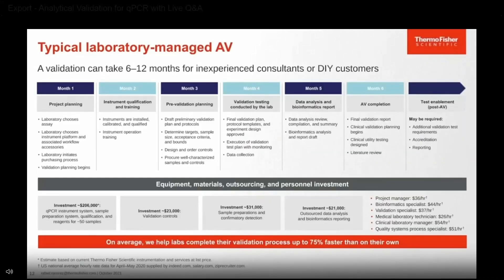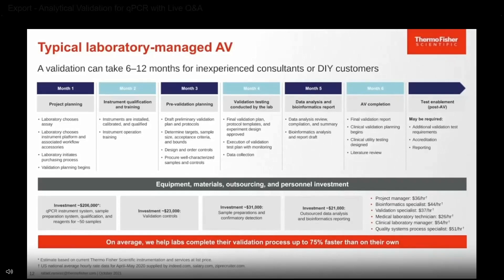Here is a timeline on how long it takes inexperienced consultants or DIY customers to execute a validation — we average between six to twelve months. Month one is dedicated to project planning: deciding on assay content, instrumentation, and workflow, and initiating the PO process. Month two is instrument qualification and training. Month three is pre-validation planning — drafting preliminary validation plans and protocols, determining samples, acceptance criteria, and designing and ordering controls. Month four is finalizing the validation plan, starting execution, and data collection. Month five is dedicated to data analysis. Month six, you complete your validation report and begin clinical validation planning and testing, followed by submitting documentation to your accrediting organization.